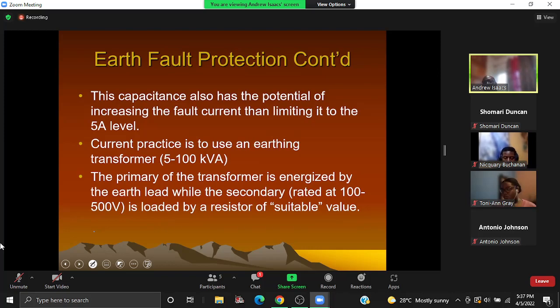You with me? And the secondary of the same earthing transformer, I will give it a rating here, 100 to 500 volts, is passed through a resistor. Are connected to our resistor. So we energize the primary using the output from the current through the earthing lead. Yes? And the secondary, we connect it across our resistor.